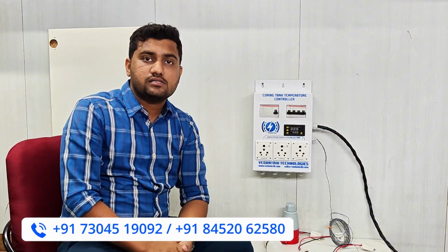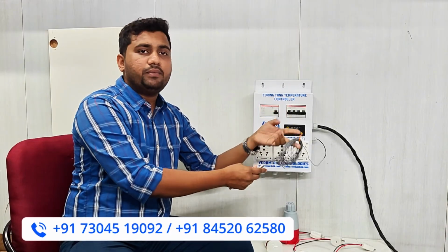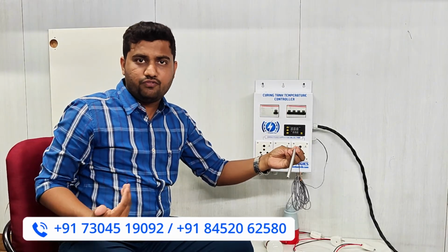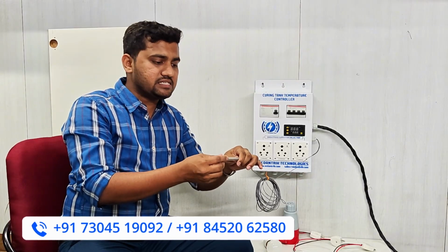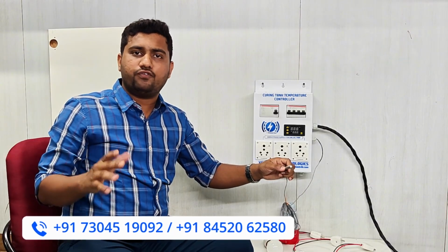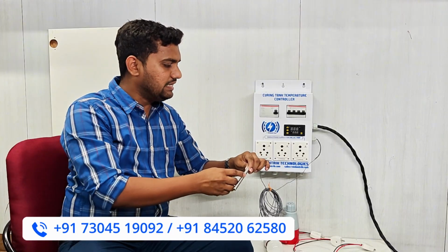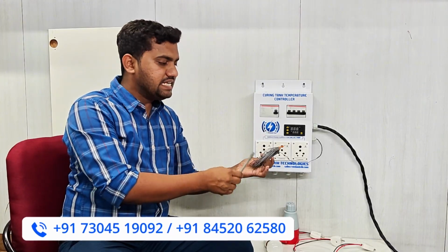Now the question arises: since there is only one sensor, the sensor will be in any one of the tanks. We do not have 4 sensors because this is not having independent control. If the temperature sensed by this sensor goes above 29 degrees Celsius, all the heaters will be cut off simultaneously because it has only one input of the sensing element.